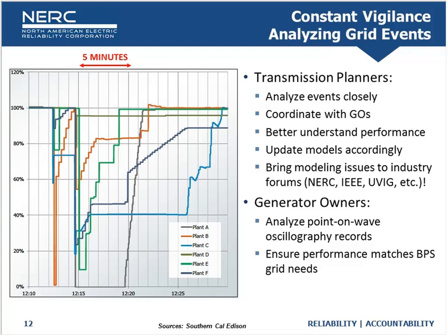Here you can see two different events that happened about two minutes apart — first at 230 kV, one at 500 kV. The plants responded very differently. Note that these are one-minute divisions, so this is a long period of time for our dynamics realm. You can see capturing momentary cessation here — this plant went near zero output instantaneously and came back. Others are seeing ramped responses back over a period of minutes, and we're looking very closely at why these plants are performing that way.